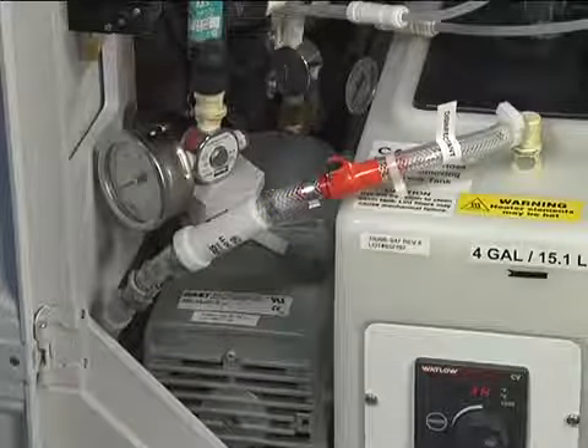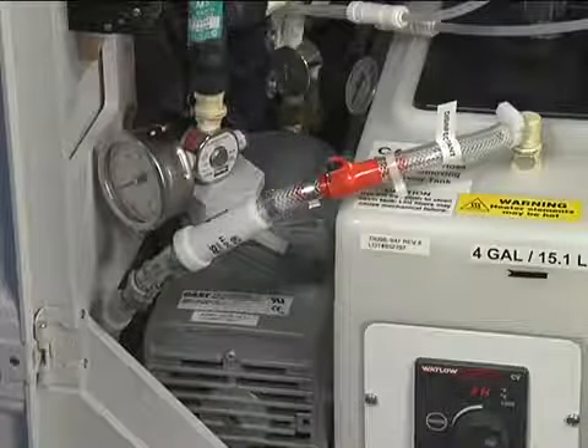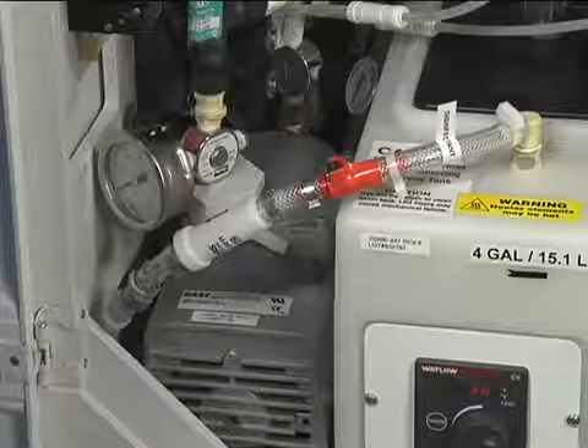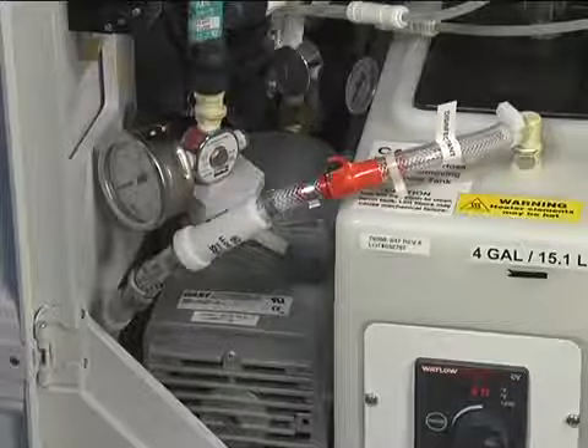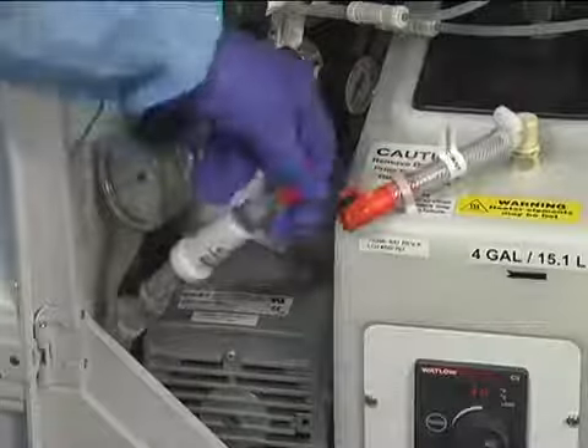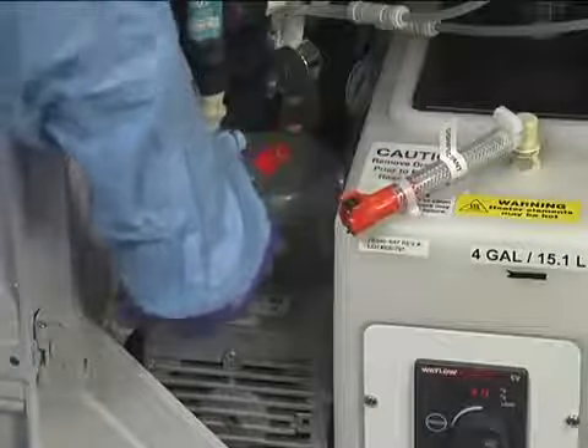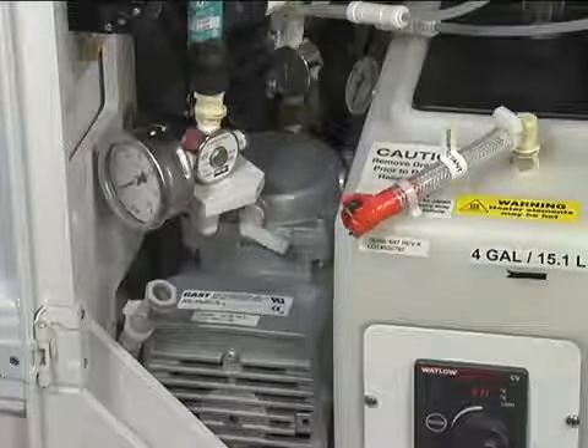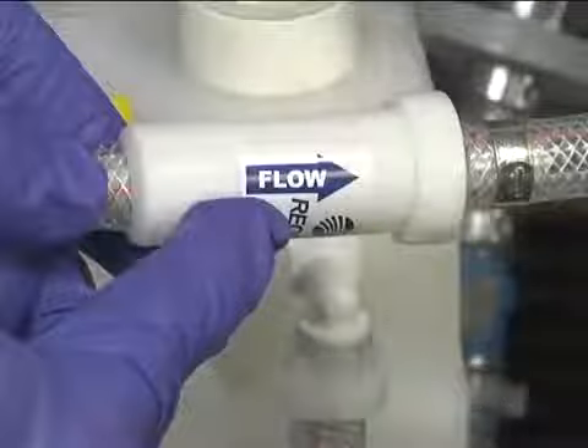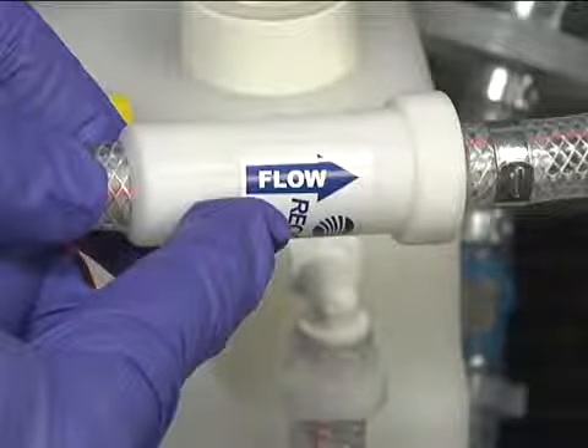Before changing the disinfectant filter, place an absorbent cloth under the filter connections to catch any remaining solution. Undo the quick connect fitting from the reservoir side of the filter. While holding the filter, undo the quick connect fitting from the pump side of the filter. The arrow on the filter, which indicates the direction of the flow, should point towards the pump.